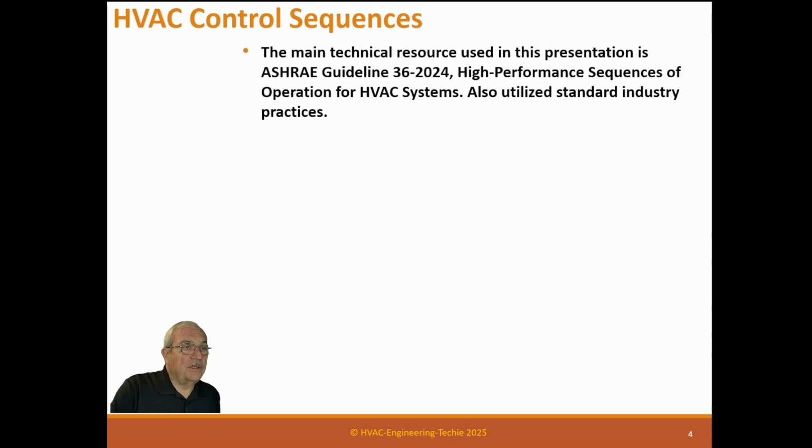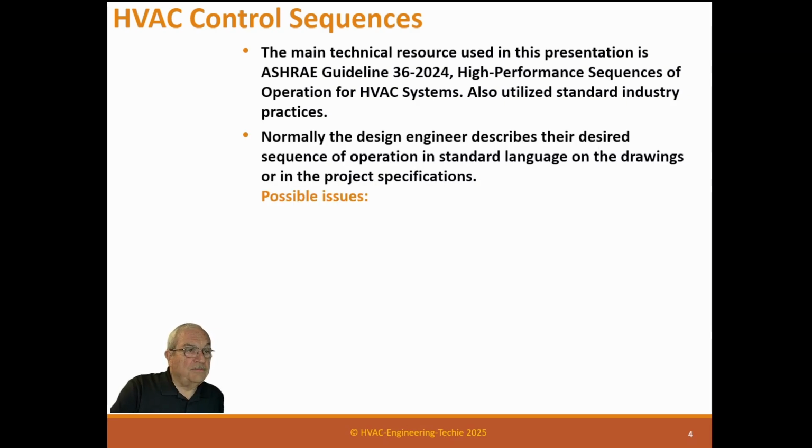All right, today we're going to talk about outside air systems. Now, the main technical resource used in this presentation is ASHRAE Guideline 36-2024. It's a high-performance sequence of operations for HVAC. Also, we utilize standard industry practices. Now, we use ASHRAE mainly for the reset sequences, which has been problematic in the industry. Otherwise, they're pretty well industry standards.